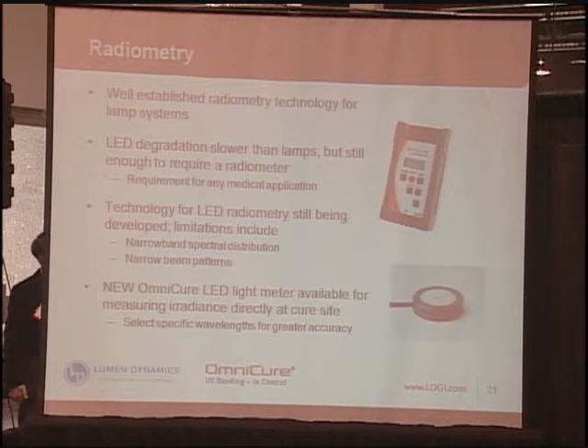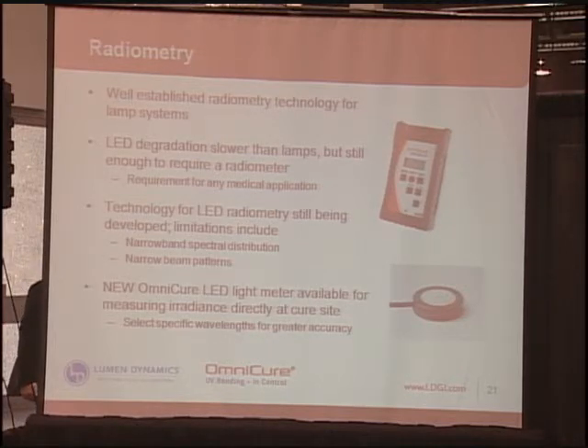So finally, we'll talk a little bit about the radiometry. Again, lamp systems have been around for years. The radiometry is very well established. There's a number of radiometers out there that work very well for measuring the output from your lamp-based systems. So although LEDs we saw degrade much slower than lamp-based systems, they do still degrade, and it's still very important that you're monitoring and measuring the output from your system. The challenge with LEDs is that unlike the lamps, one, they're a very narrow spectrum, but two, it's also very narrow beam patterns, and both of these present challenges for radiometers.